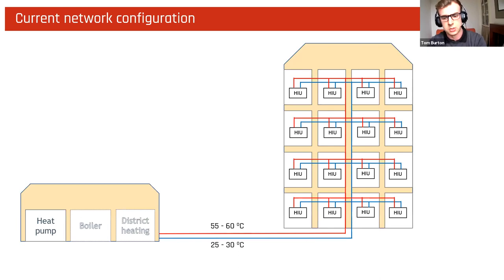So before we start talking about the issues, this is a schematic that should be familiar to most people. This is what networks typically look like currently. You've got one riser per building, per core, and then long laterals on every floor, and HIUs are located internally to flats, typically in utility cupboards. That's what things currently look like. The temperatures we've now managed to drop to 55, 60 flow, 25, 30 return. That has been spoken about in the first session, and there'll be more information about it in the third session as well.